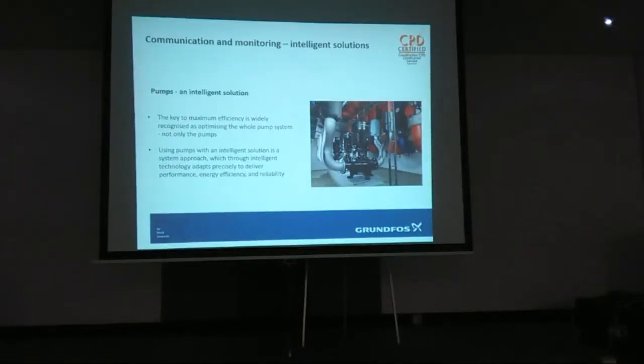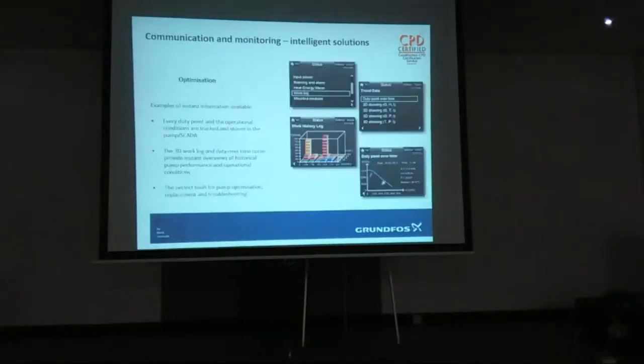A lot of people still put volt-free contacts in for start, stop, a fault condition and, obviously, power, and then put a BACnet card on it to actually monitor what's going on, when everything could be driven through the BACnet card. I think people are not quite 100% happy with the network SCADA system. We'd like to keep the old hardwire system a little bit, but you can do both. On larger pumps, you probably have a separately mounted inverter. On smaller pumps up to about 22 kilowatts, you've got the option of it built on, from all manufacturers usually.